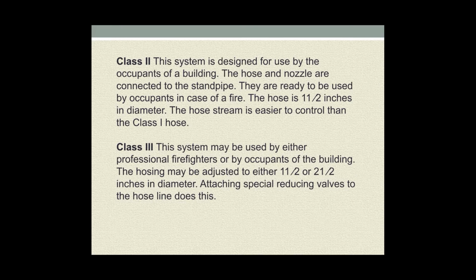Class 2. This system is designed for use by the occupants of a building. The hose and nozzle are connected to the standpipe. They are ready to be used by occupants in case of a fire. The hose is 1 1/2 inches in diameter. The hose stream is easier to control than the Class 1 hose.